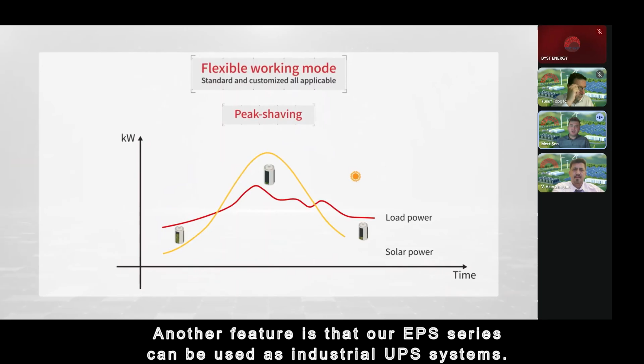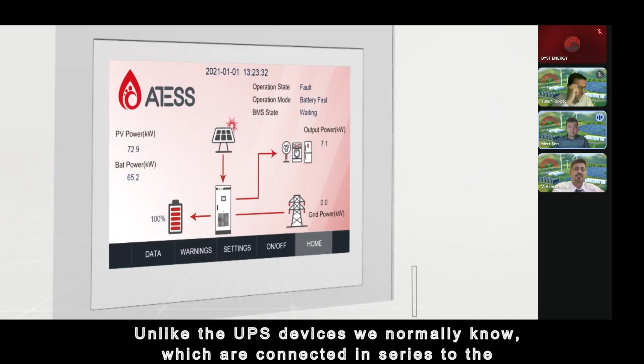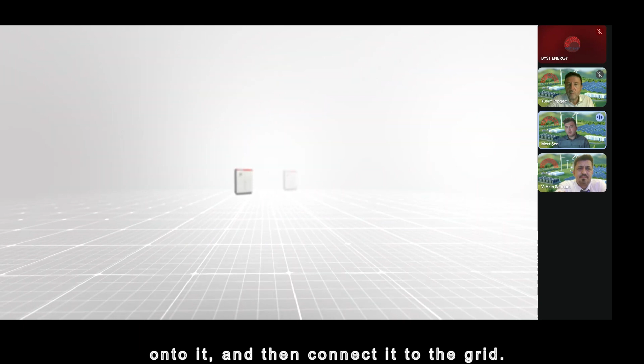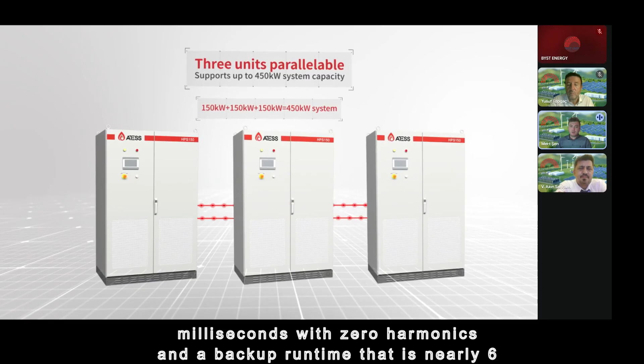Another feature is that our EPS series can be used as industrial UPS systems. What does industrial UPS mean? Unlike the UPS devices we normally know, which are connected in series to the system, we connect this device directly to the solar array, load our battery group and hybrid inverter onto it, and then connect it to the grid. And when the power goes out, we offer a switching time of less than 10 milliseconds with zero harmonics and a backup runtime that is nearly 6 to 7 times longer than a standard UPS. What does this mean? 6 to 7 times longer than the standard.